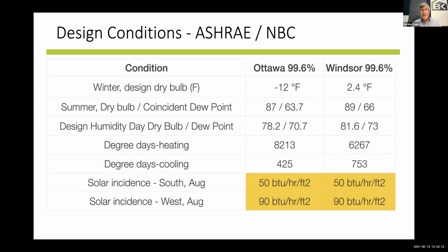And guess what? The CSA F280 standard takes into account wind. When we give you this design day, within the algorithms, it also gives us a sense of the wind that's happening on that day. There's a wind effect built into the heat loss, heat gain calculations. So just put in the minus 12. Don't put in what the weather person said it felt like on that given day.